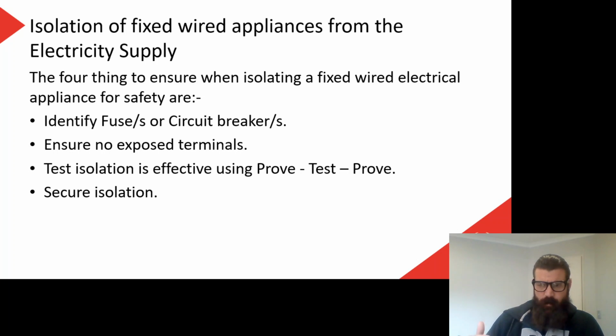But we can just do it by trial and error, by physically testing that socket, go to the switchboard, switch one off, come back, test the socket again, and so on. We need to ensure there's no exposed terminals. We need to test our isolation is effective using the prove, test, prove method.